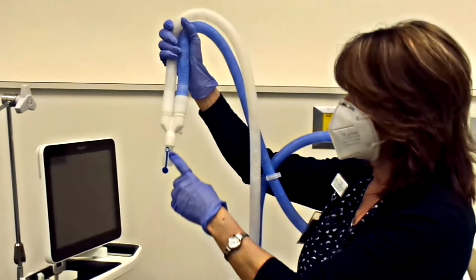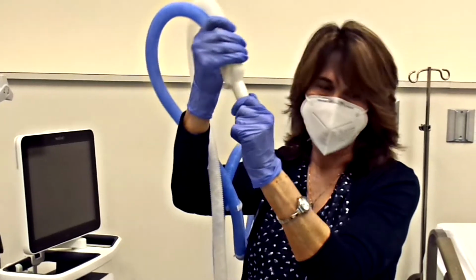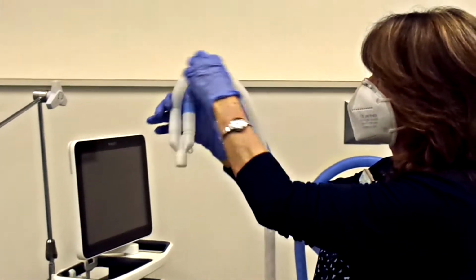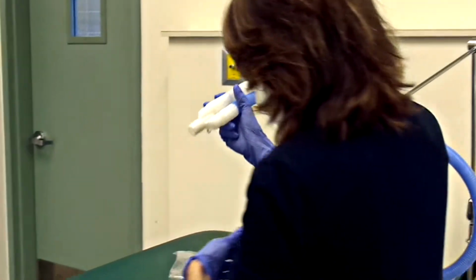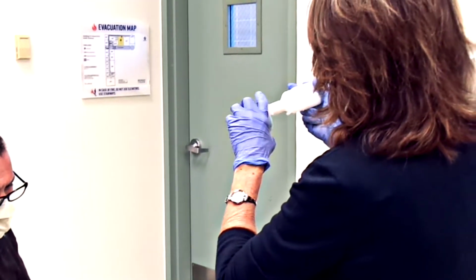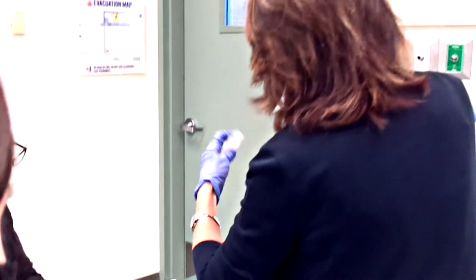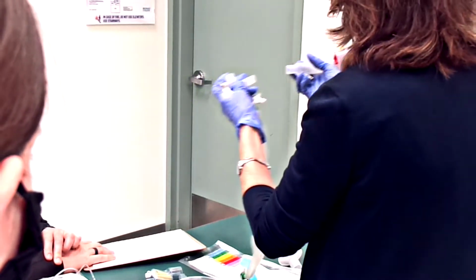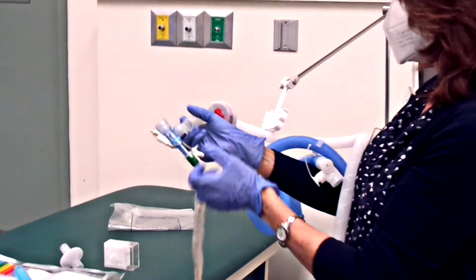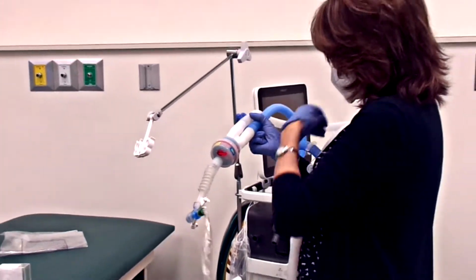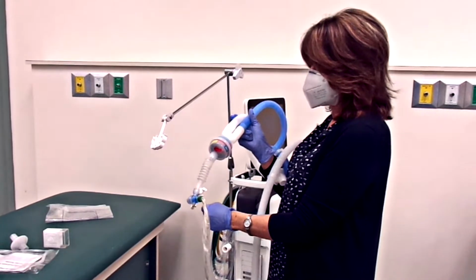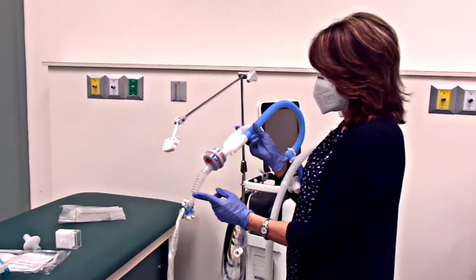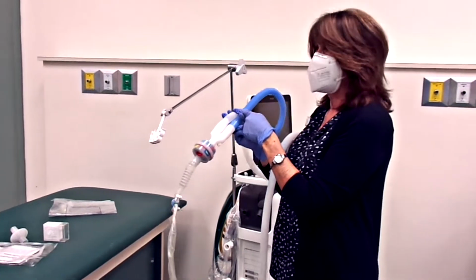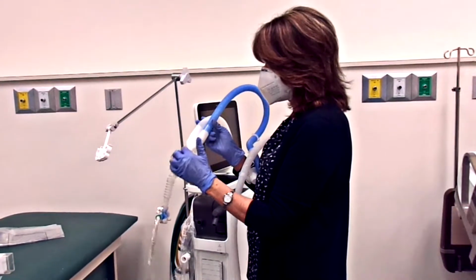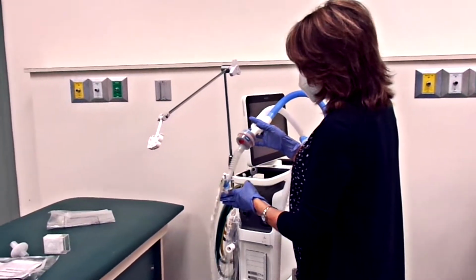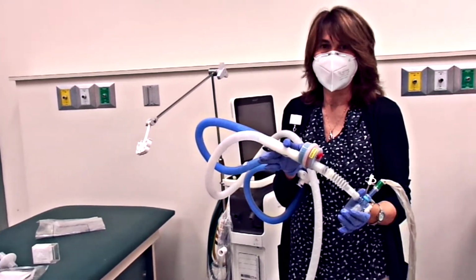So when you have fresh air coming in, it goes to the patient, and then when the patient exhales, it goes out the expiratory tubing. So when you have, let me add a bunch of stuff to it. Tubing, make it long, exaggerate the point. So we have a fresh supply of gas coming to the patient, going into their endotube, their trach tube, and then the patient exhales. Their exhaled air will fill this up, it'll fill this up, it'll fill this up, and then go out this way. Now it's time for the next breath. The next breath will come in and push all this air back into their lungs. So between the Y and the patient, that's all considered rebreathed air. And another name for rebreathed air is dead space air.